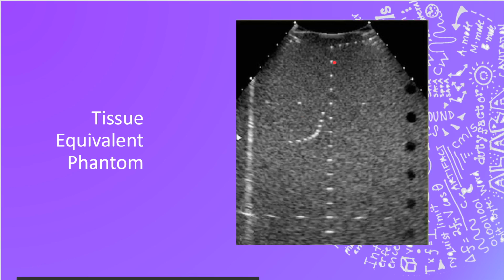But look, as we get further into our field, we start to get wide dashes. And we can see that our focus is right here. So look what's happening. Right at our focus is where we're getting that best reflection. And then they start to get wide because lateral resolution is worsening. So those vertical dots not only tell us about vertical registration, but they also give us an idea about lateral resolution. So lateral resolution and vertical registration.